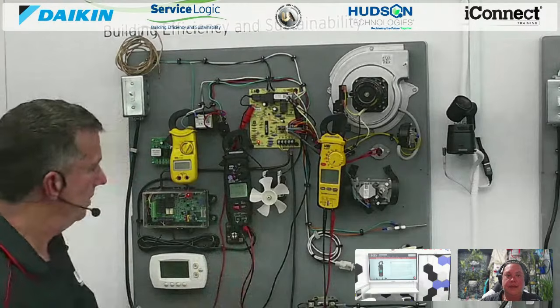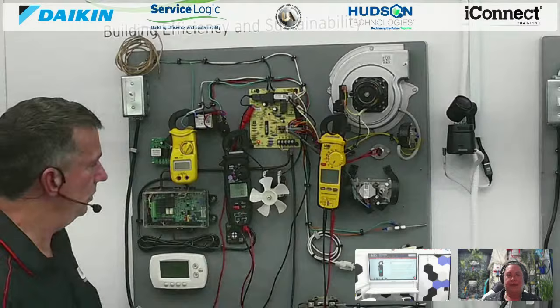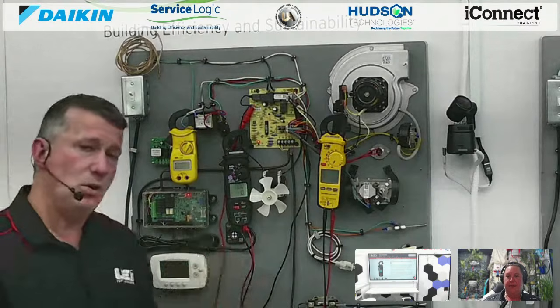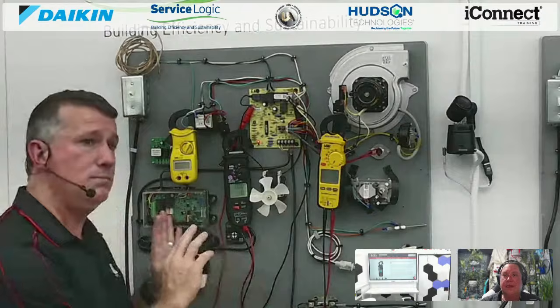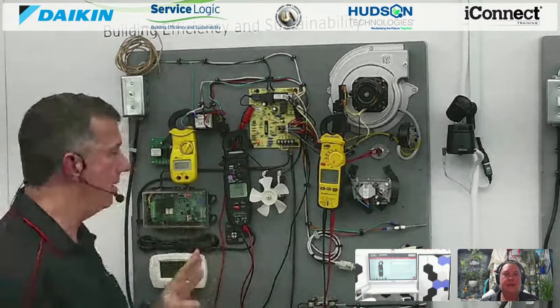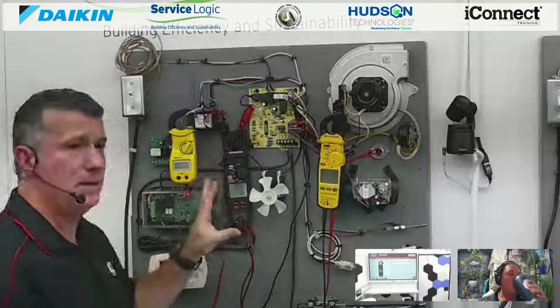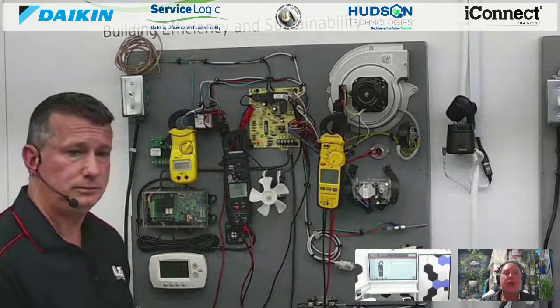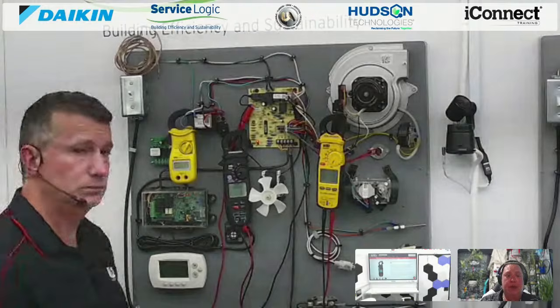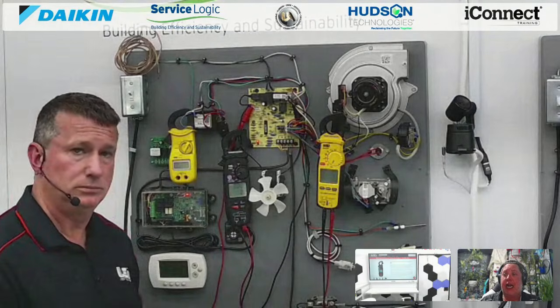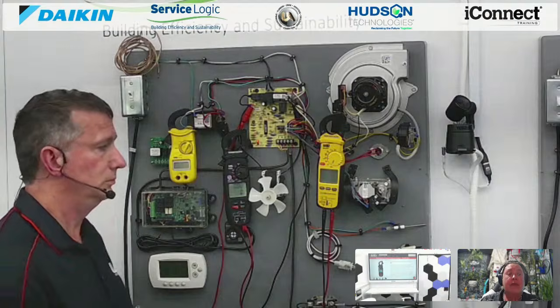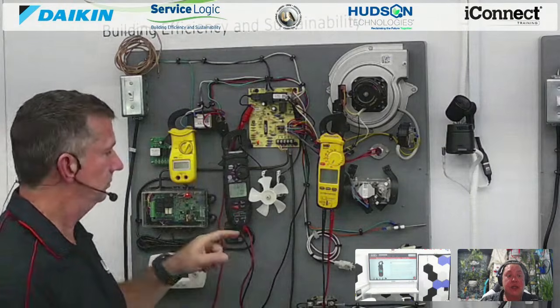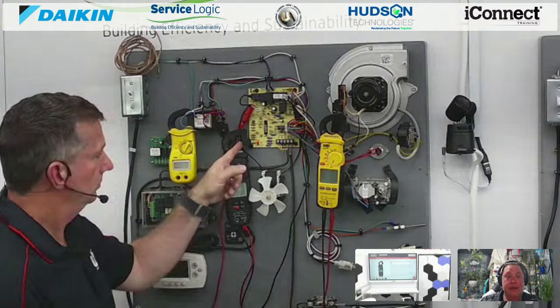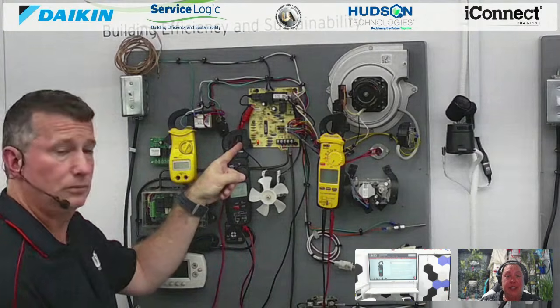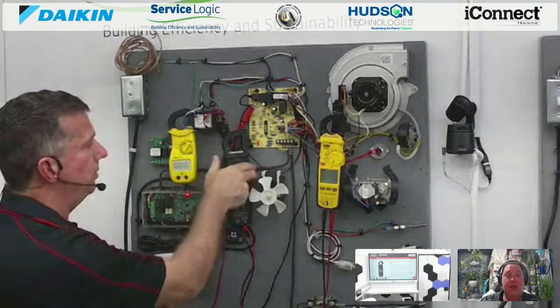Okay, so I have now moved over into my wattage power factor. So Luis, let's talk about how we measure wattage. Let's start there so that we understand where our meter is going to be connected. Watts, just for the definition of it, is your amps times your volts. So you're going to want to get your amp draw, and that's going to come through your amp clamp. We've clamped onto a primary lead of our motor in this case.